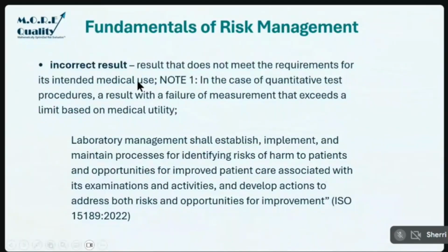An incorrect result, the edge of the cliff, is a result that does not meet the requirements for its intended medical use. In the case of a quantitative test, it's a result with a failure of measurement that exceeds a limit based on medical utility. That is from CLSI. So very clearly, your purpose is not to measure statistics, it's to measure medical acceptability of the results that you're turning out.